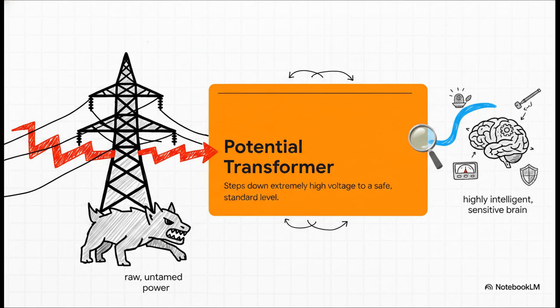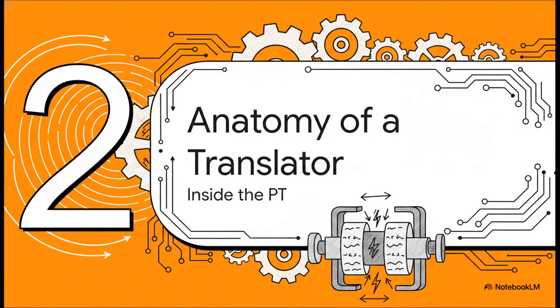This is a highly specialized instrument transformer used explicitly for stepping down that extreme high voltage to a safe standard level, typically that 110-volt whisper we just talked about, for measurement and protection. It is the ultimate translator. It stands squarely between the raw, untamed beast of grid power and the highly intelligent, sensitive brain of our modern monitoring systems. Moving on to Section 2, Anatomy of a Translator.